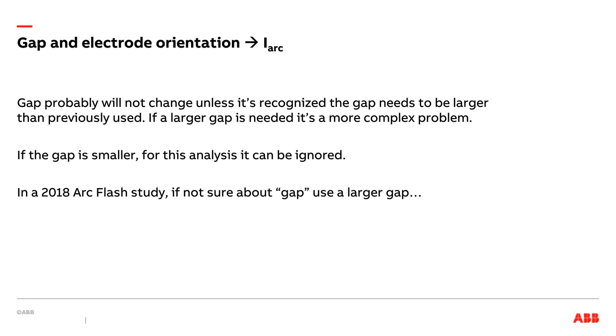If you know the gap is going to be a lot larger, that kind of throws a wrench in the works because now you get less arcing current, harder to detect, and you get more energy per unit time, potentially a more hazardous situation. The method I'm going to discuss does not deal with that possibility. It assumes that the gap is going to be the same or smaller.